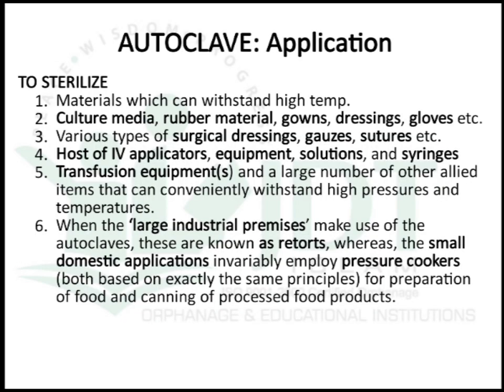The autoclave is mainly used for sterilization of materials that can withstand high temperature, including culture media, rubber materials, gowns, dressings, gloves, various surgical dressings, sutures, IV applicators, equipment, solutions, syringes, transfusion equipment, and many other items that can withstand high pressure and temperature. In large industrial settings, autoclaves are known as retorts. For domestic applications, a simple pressure cooker can be used for steam sterilization.